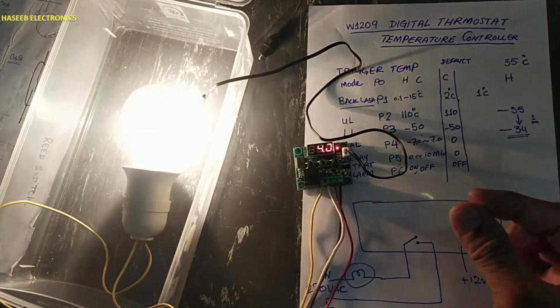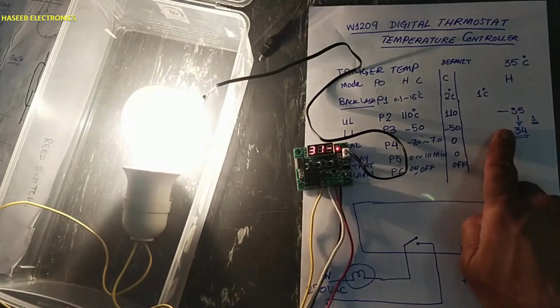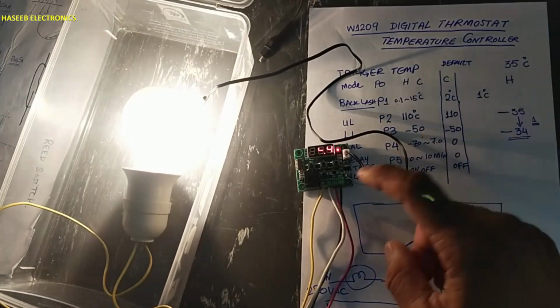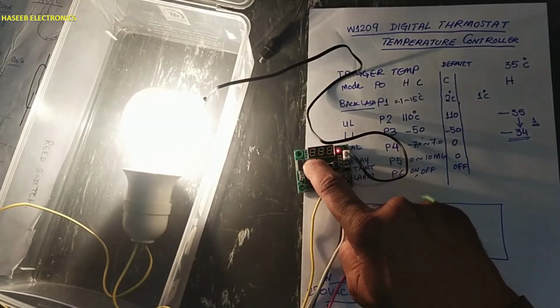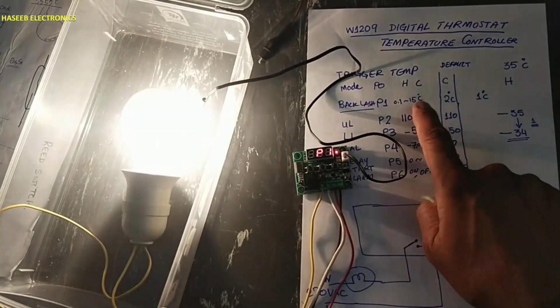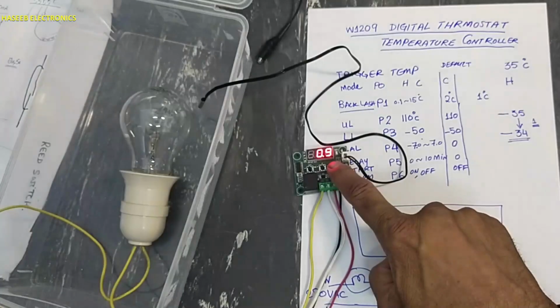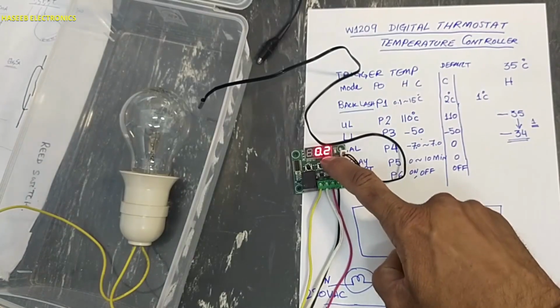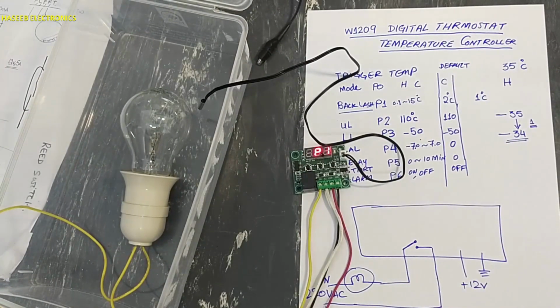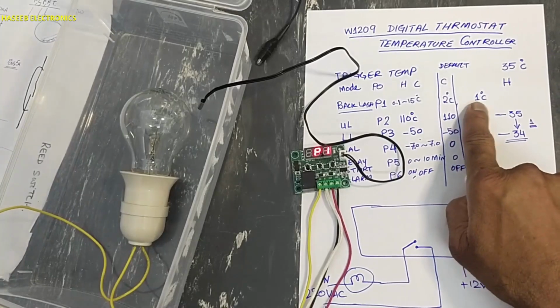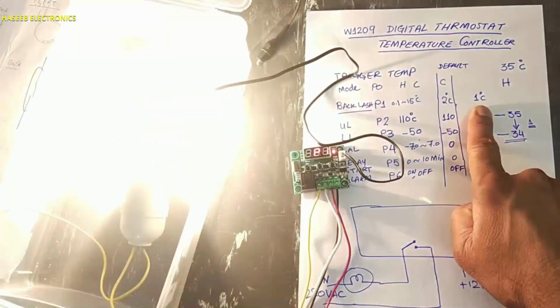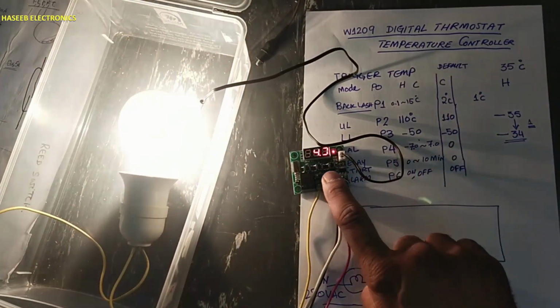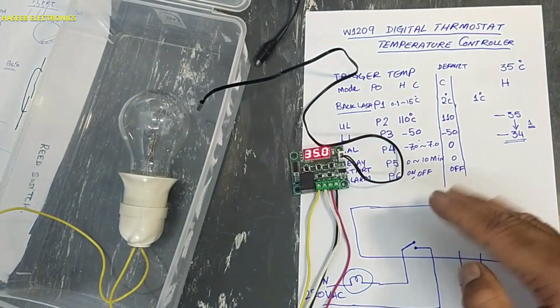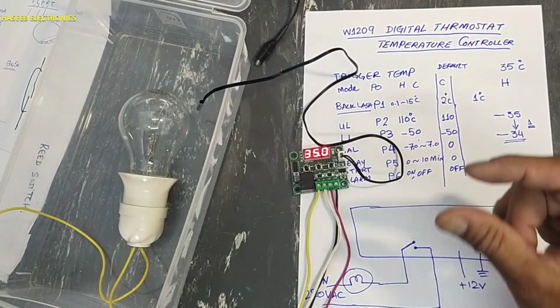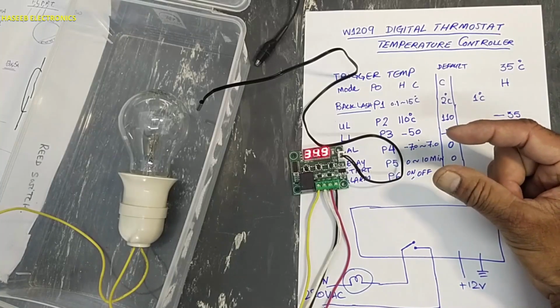If you want to control the temperature with 0.2 degrees margin, 34.8 to 35 degrees, press set button, go into P1, set, point 2, set. Now we adjusted this value to 0.2. When the temperature will reach at 34.8, it will turn on. 35 off. So now it will maintain the temperature within very close window. Yes.